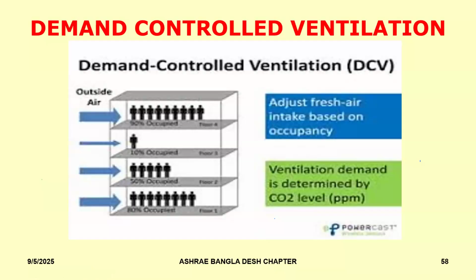How do we monitor this? We could monitor this based on occupancy sensing or occupancy counting, or we simply go by what is the actual CO2 level in the space. The higher the CO2 level, that gives a good proxy for us to decide how many people are within the space. Higher CO2 concentration means higher occupancy level. Or if space-generated volatile organic compounds are more at that point in time, that means a requirement of higher outdoor air. So that's that component that we talk about.